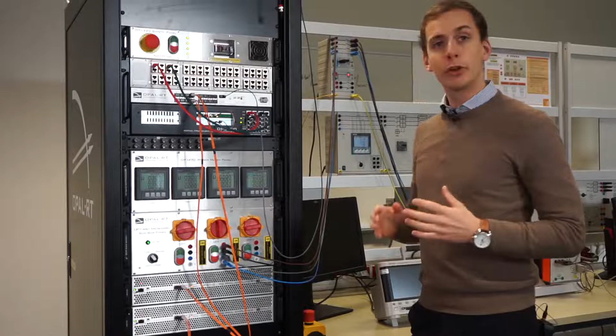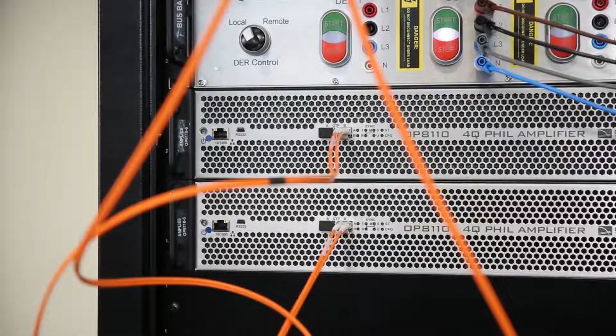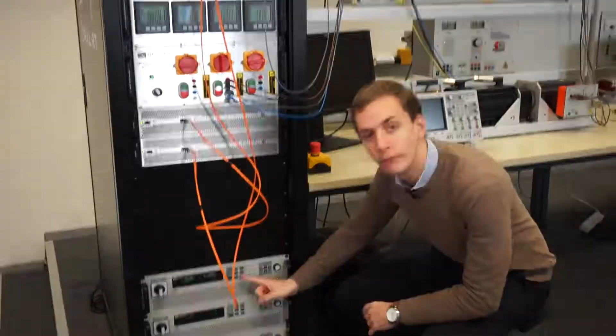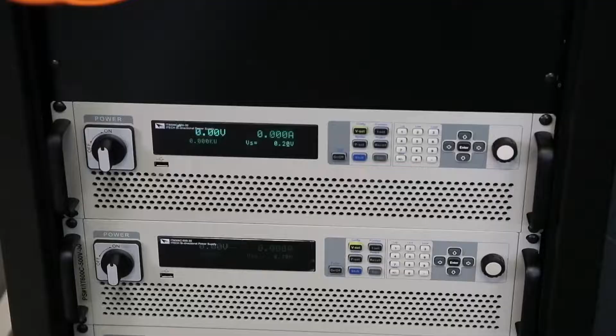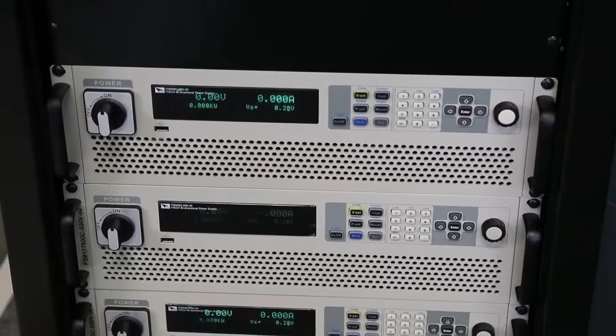In terms of fidelity, the bandwidth is up to 10 kilohertz at -3 decibel, and total harmonic distortion lower than 0.5%. In terms of safety, we have, for example, over voltage, over current, under voltage, short circuit, and over temperature protections. In terms of connectivity, optical fiber links are connected between these power amplifiers and the real-time simulator. It uses small form factor pluggable connectors, and to ensure very fast communication, the Aurora communication protocol is implemented within the simulator FPGA and within the power amplifier FPGA. So we have a communication higher than 5 gigabits per second, which is key to ensure the stability of the power hardware-in-the-loop setup.